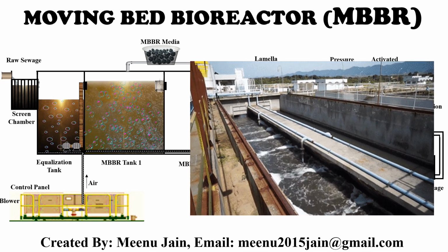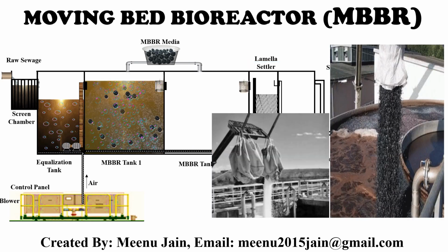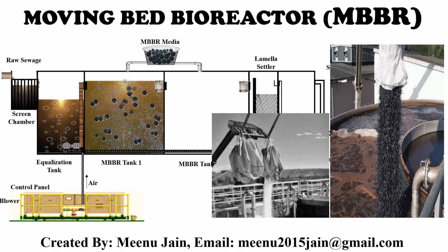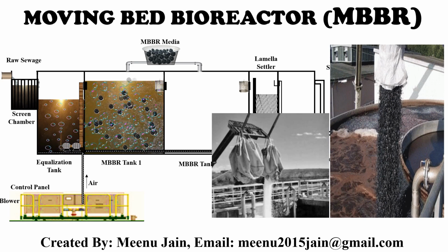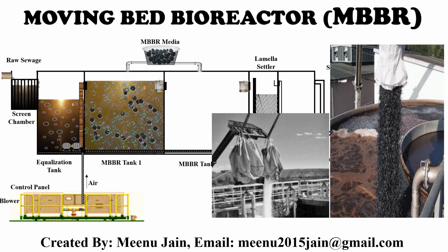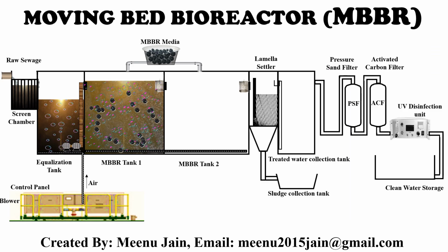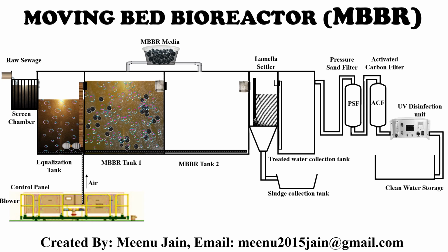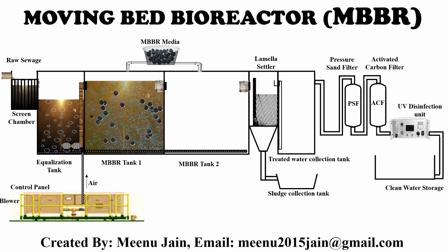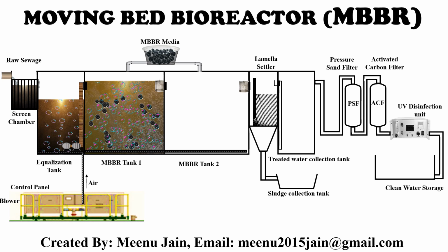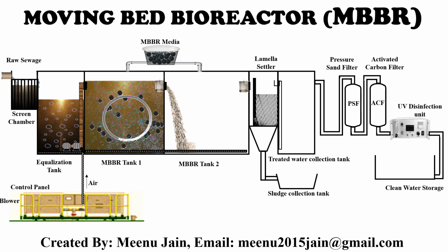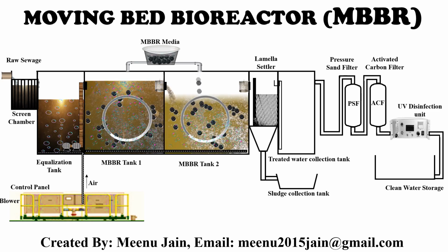The moving bed biofilm reactor, or MBBR, consists of an aeration tank like an activated sludge tank with special plastic media that provide a surface where microorganisms can grow as a film. These carrier media are dumped in the aeration tank and mixed with the effluent liquid by the aeration system. Aeration is provided to continuously circulate the plastic media and to maintain the dissolved oxygen level in the MBBR tanks. Proper aeration leads to good contact between the BOD or organic material and the biomass or microorganisms on the carrier media.